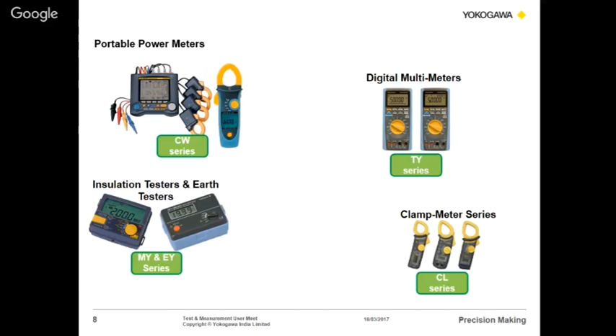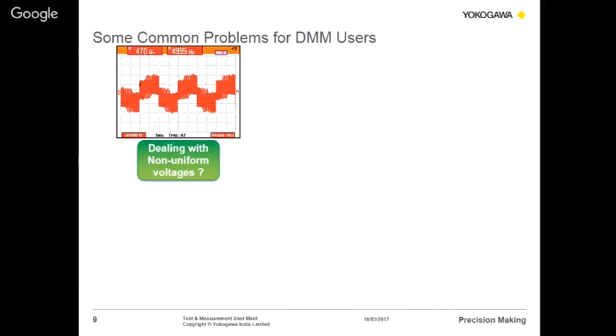Some common problems of multimeter users. It is not always a uniform waveform. Sometimes, if you are talking about a drive system, it will be pulse width modulated waveforms. So it is not 50 hertz or 60 hertz. If the harmonics are high, instead of a sine wave we get a square wave. So those are the non-uniform voltages users have to deal with, and they also worry about wrong connections.